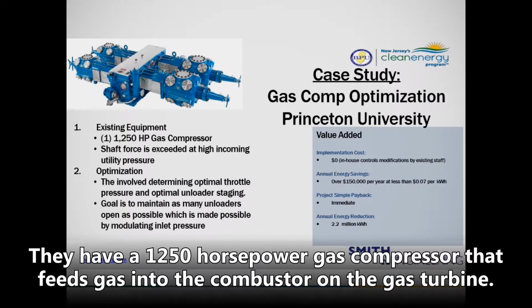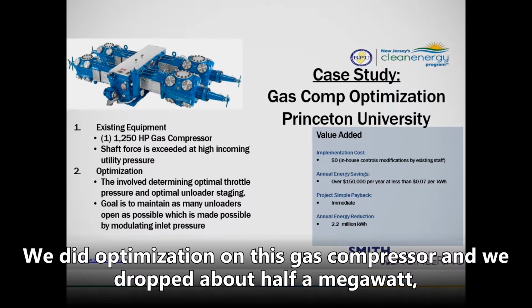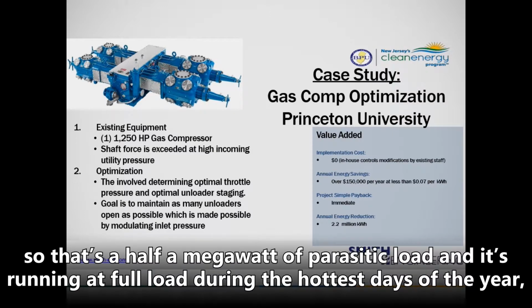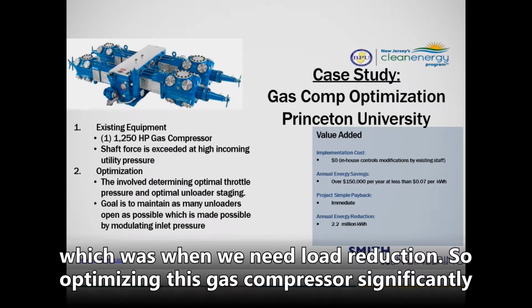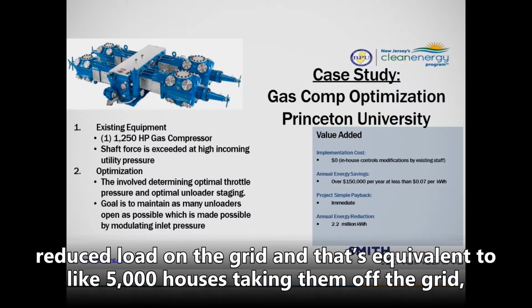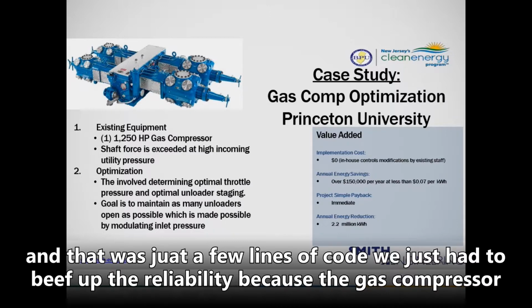So they have a 1,250 horsepower gas compressor that feeds gas into the combustor on the gas turbine. We did optimization on this gas compressor, and we dropped about half a megawatt. So that's half a megawatt of parasitic load, and it's running at full load during the hottest days of the year, which is when we need load reduction. So optimizing this gas compressor significantly reduced load on the grid, and that's equivalent to like 5,000 houses, taking them off the grid. And that was just a few lines of code.